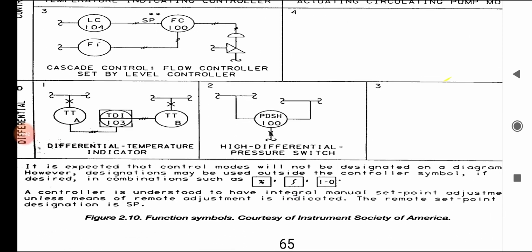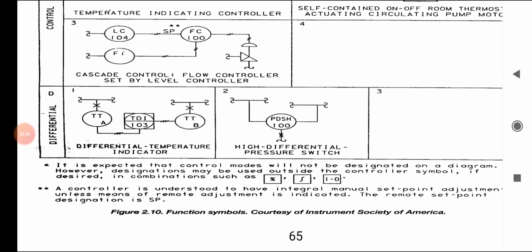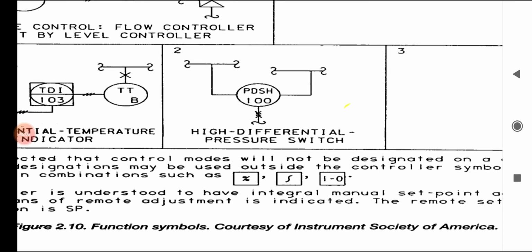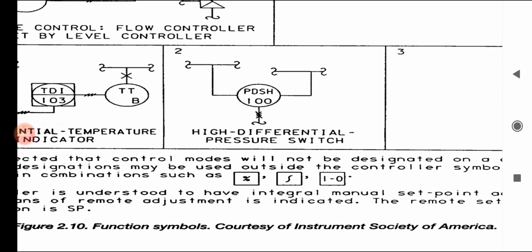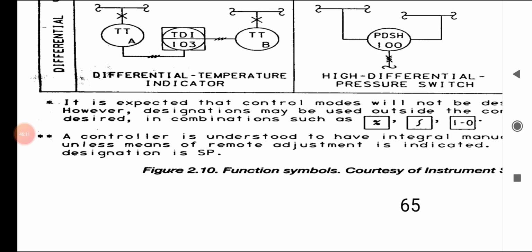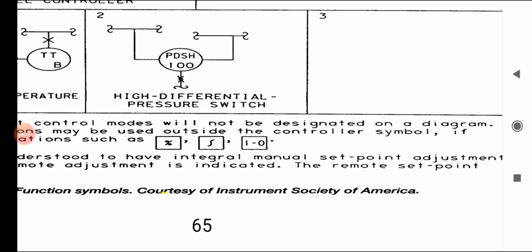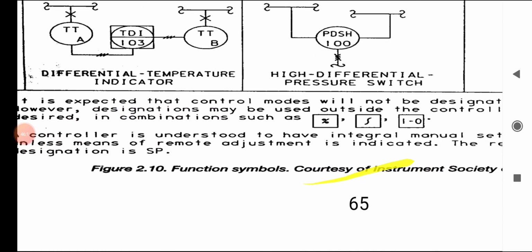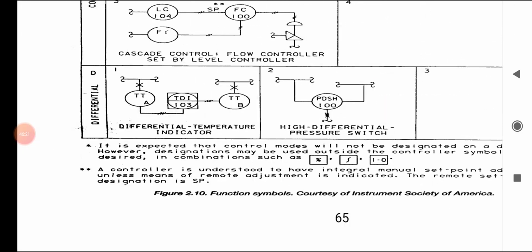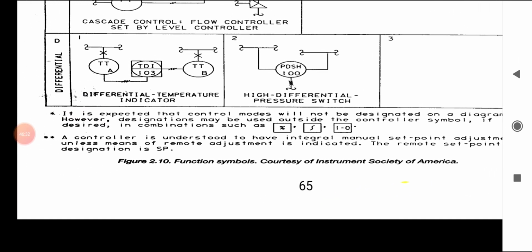It is expected that control modes will not be designated on the diagram. However, designations may be used outside the controller symbol if desired, in combinations such as the symbols shown: percentage, S, input and output. A controller is understood to have an integral manual set point adjustment unless means of remote adjustment is indicated. The remote set point designation is SP.